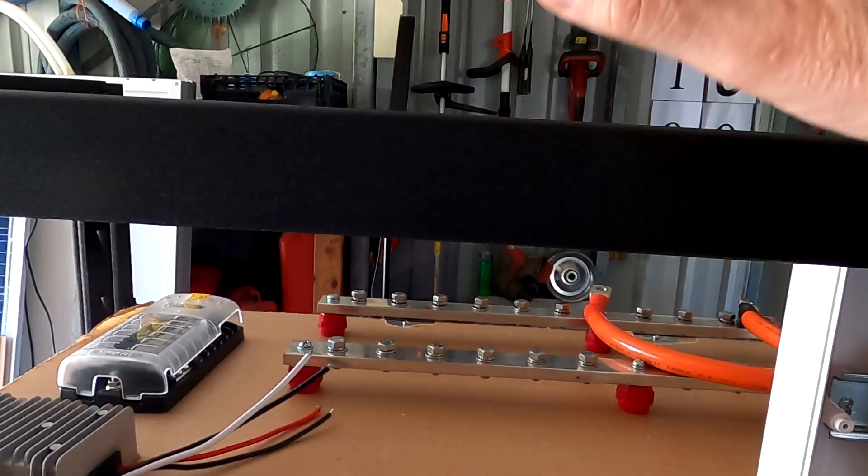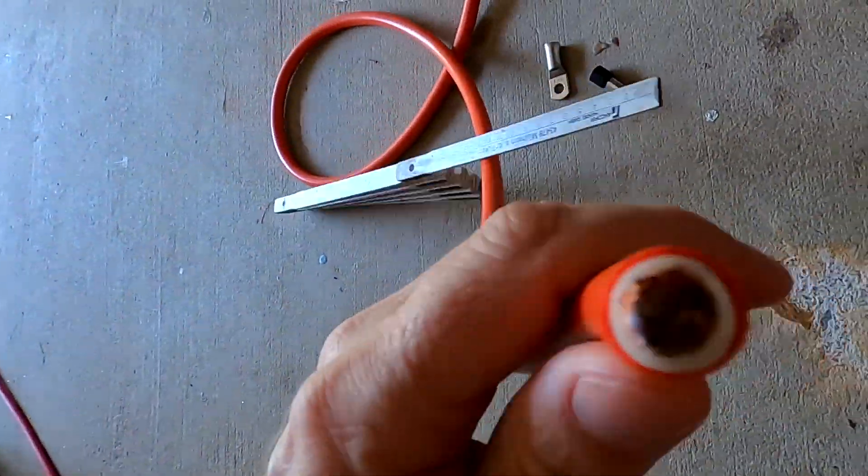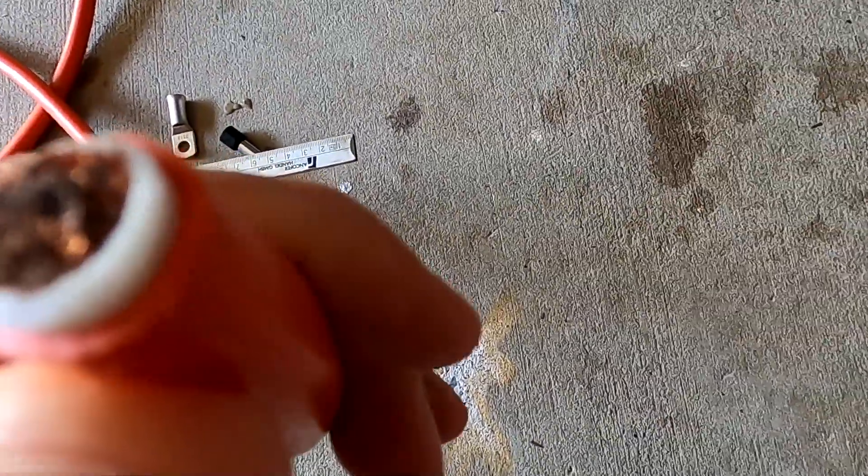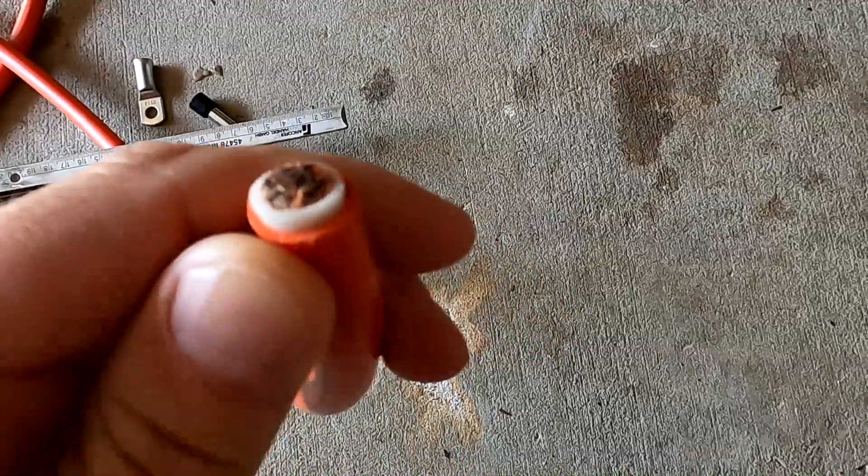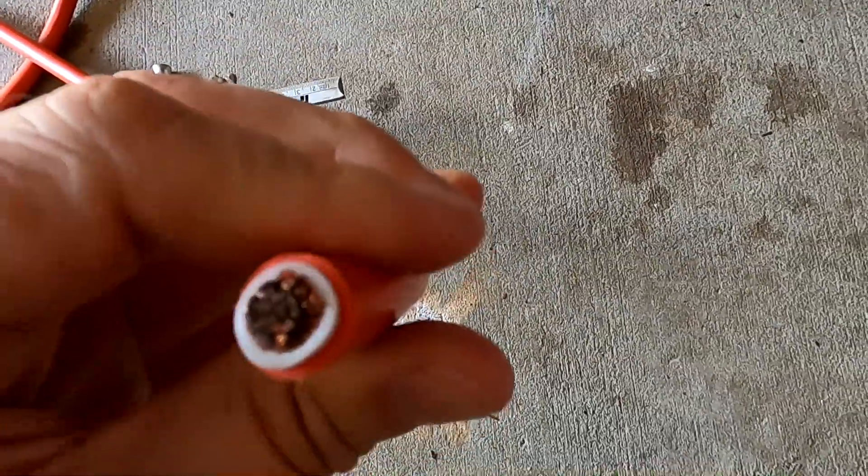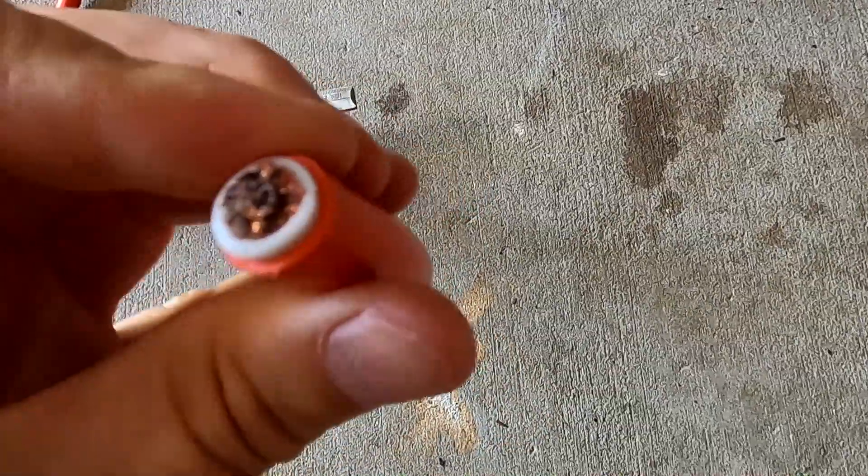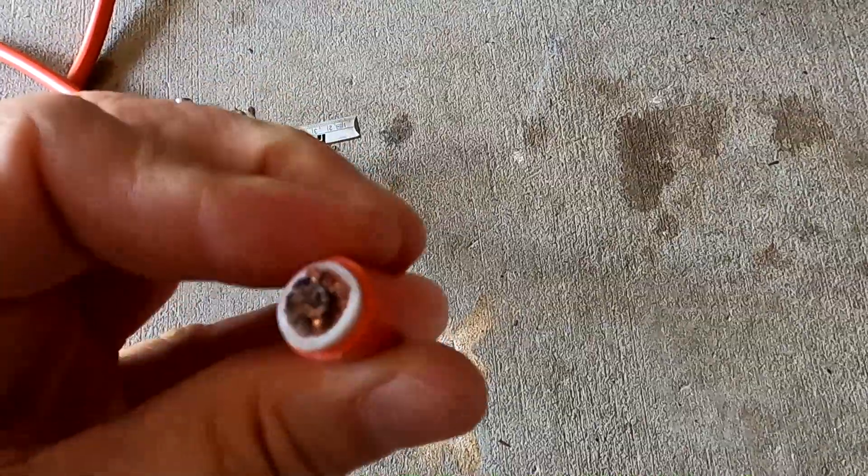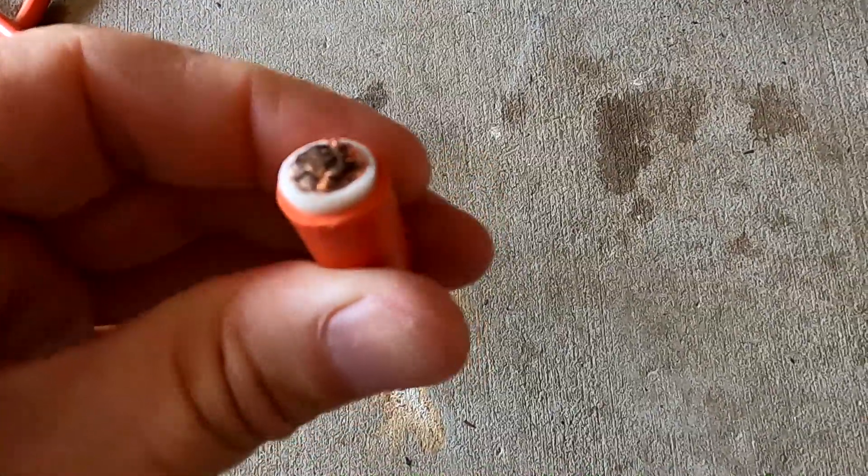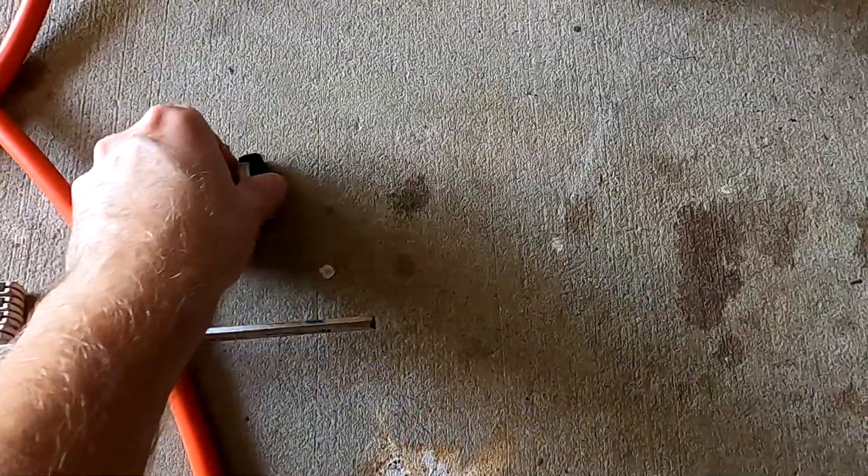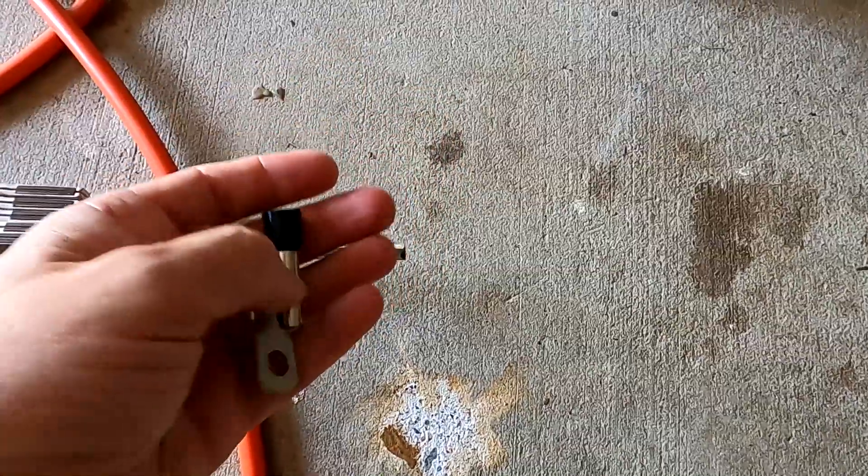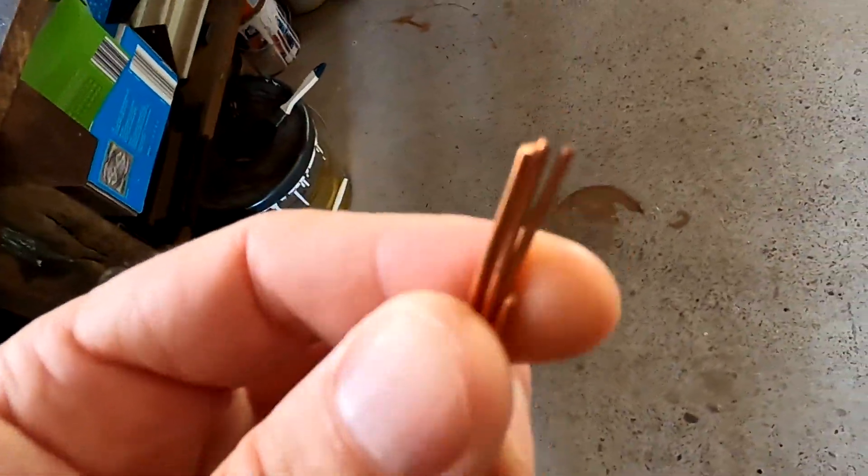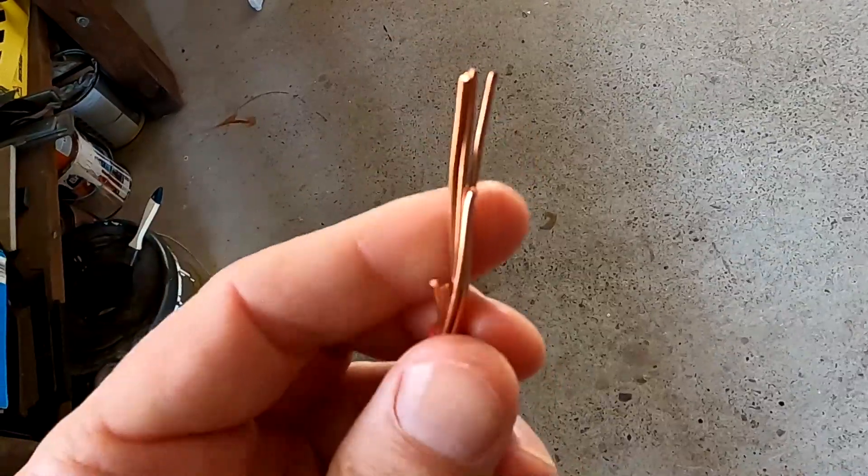Some other people suggested don't use any ferrules at all, just use the bare copper and connect them to the circuit breakers. It gives you more flexibility. While this is true, this is not allowed. We cannot have this fine stranded cable here directly connected into a circuit breaker terminal. It always needs to be terminated either by a lug or by a ferrule.